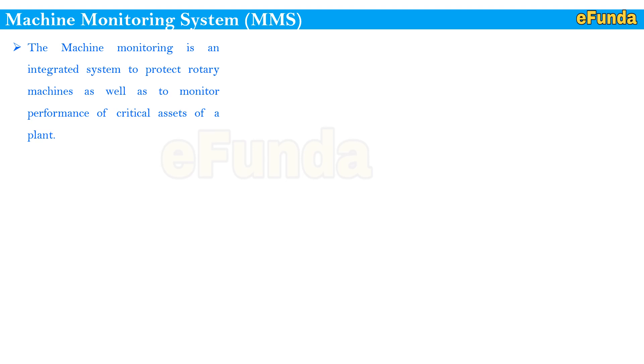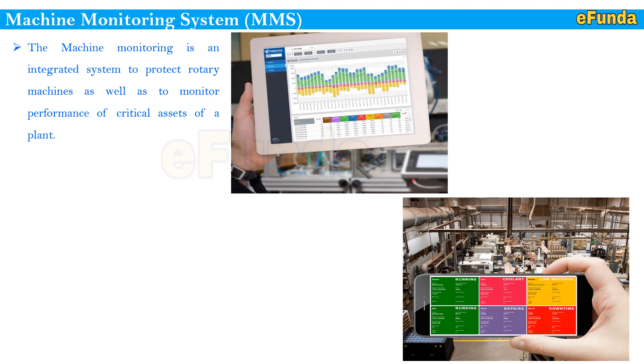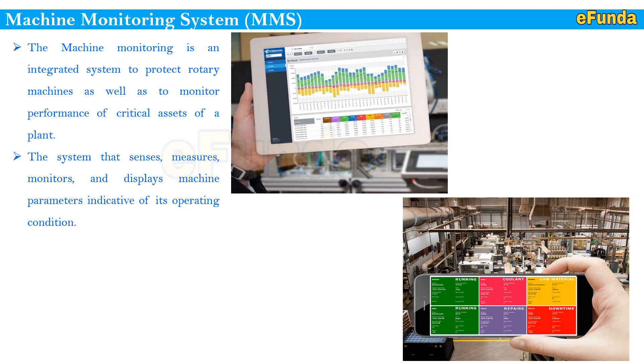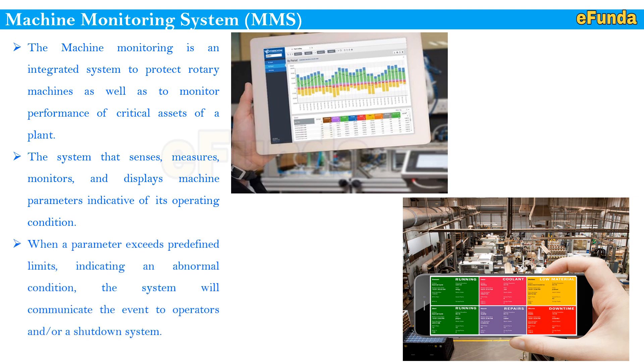Machine monitoring system is an integrated system to protect rotary machines as well as to monitor the performance of critical assets of a plant. The system senses, measures, monitors, and displays machine parameters indicative of its operating conditions. When a parameter exceeds a predefined limit indicating an abnormal condition, the system will communicate the event to the operator or take the system into shutdown. The goal of the system is to mitigate damage to the machine.